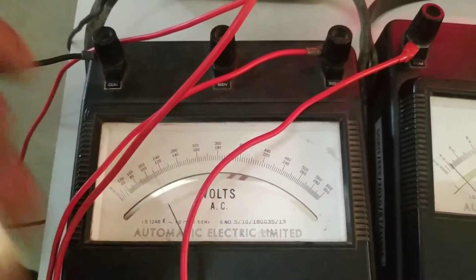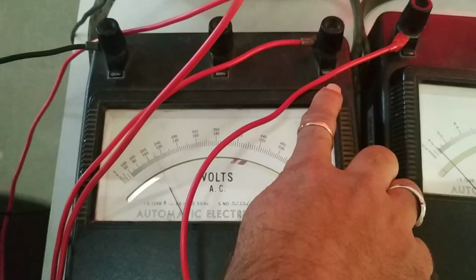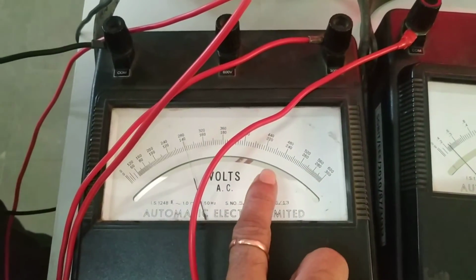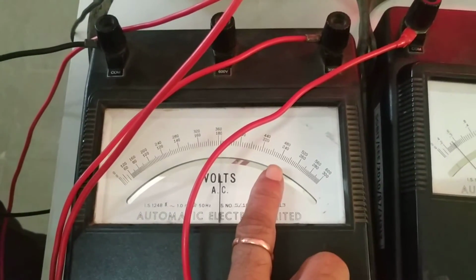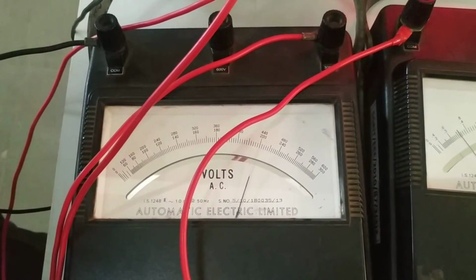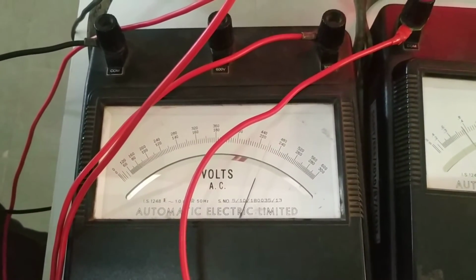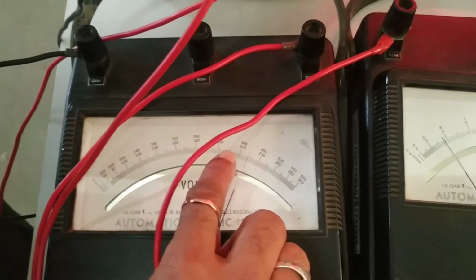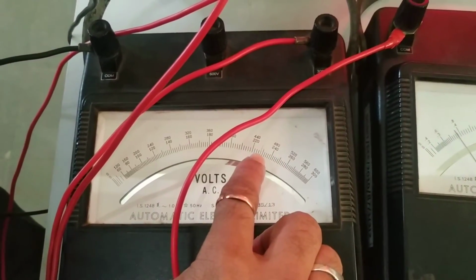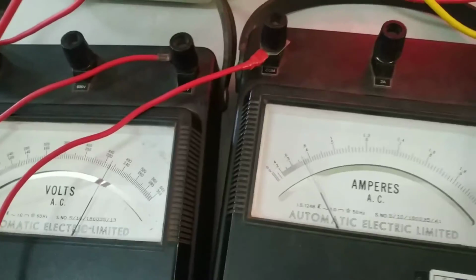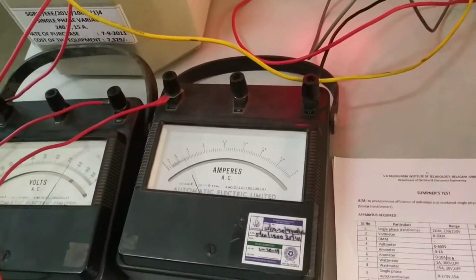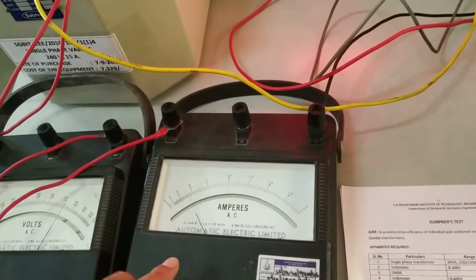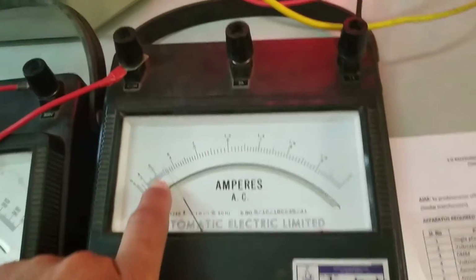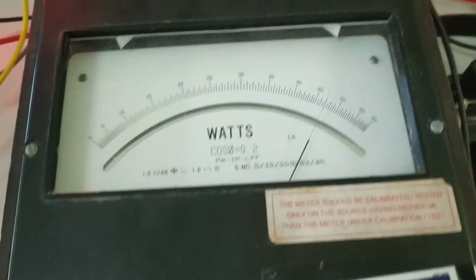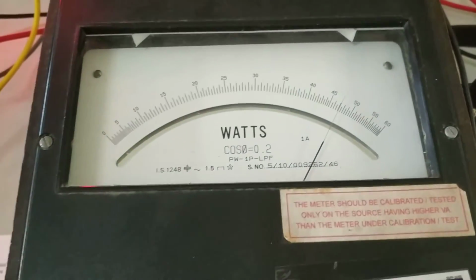So here we have selected the range as 300 volt, so we need to read the lower scale. First we need to apply the 230 volt. Now is it 230? 220, 240, in between that is 230. With respect to this 230 volt which is applied across the primary of the transformer, we are getting the current as well as the wattmeter reading. So those should be taken and put in a tabular column.